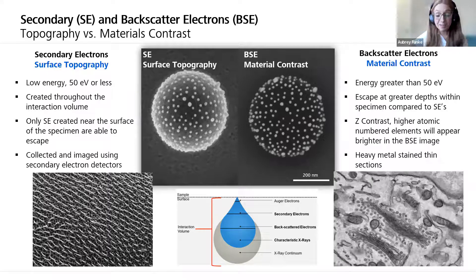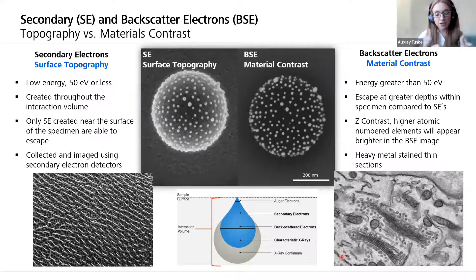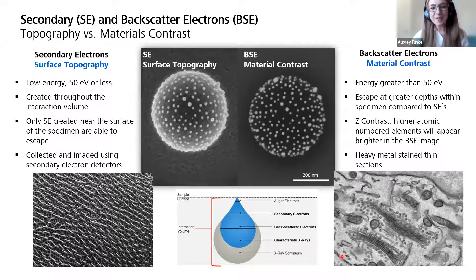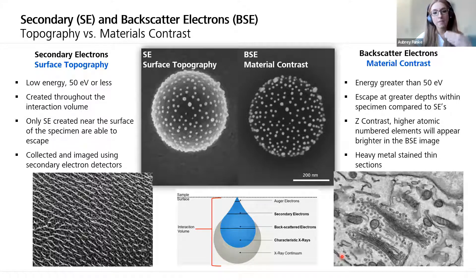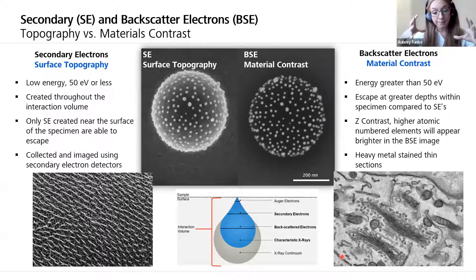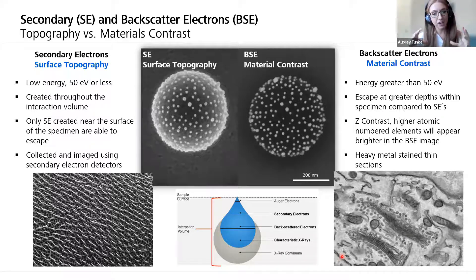This is very important for life science imaging. When getting into volume studies — taking really thin slices and building 3D renderings, whether for array tomography, serial block face, or FIB-SEM — we're using backscattered electrons to get this high contrast signal. Most biological samples aren't naturally that contrasted, so we actually add contrast by doing a heavy metal stain prior to imaging with things like lead, osmium tetroxide, and uranyl acetate. We give it this contrast that it doesn't naturally have, and then we're able to use backscattered electron detectors to get these high-contrast images.